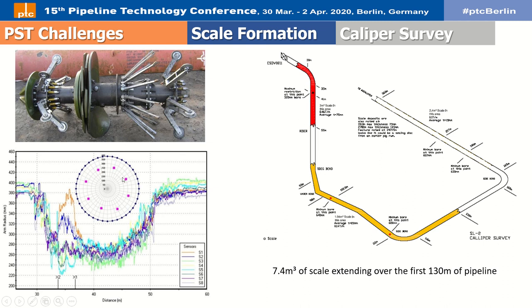The scale deposit thickness decreases further down the riser. Where the fluid temperature drops due to heat exchange with seabed water, a radius plot shows the extent and distribution of scale deposits from the bottom of the riser through the dogleg. A minimum bore of 640 millimeters — a bore reduction of 132 millimeters or 17% — occurred, and then again a localized reduction with a minimum bore of 630 millimeters over a length of almost 1 meter was observed.